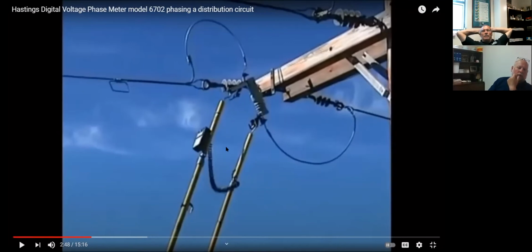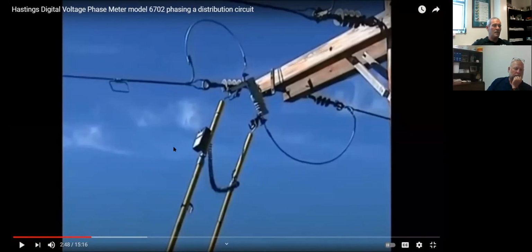Good question. What if he checked voltage here and got 7,200, or 12.5? What would be the situation? It definitely showed that there's a difference of potential, and that's not good. Right, exactly. He would be going, if they closed that switch, phase to phase. You'd have a major explosion. Good one, Lenny.